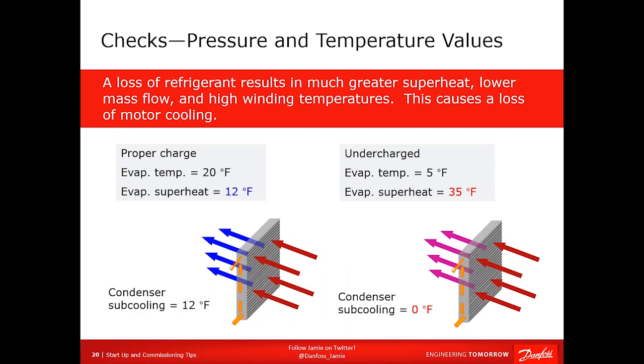Okay, let's change speed here a bit. I call it the 3 values you need to look at before you charge a system. So let's look at a TXV operating system that is operating normally. It's got a good load. So you're going to see healthy evaporator temperatures for a cooler, 12 degrees of superheat. I would say that evaporator temperature might even be a couple degrees low. At the bottom left-hand side, you've got a healthy, solid column of liquid with 12 degrees of subcooling.